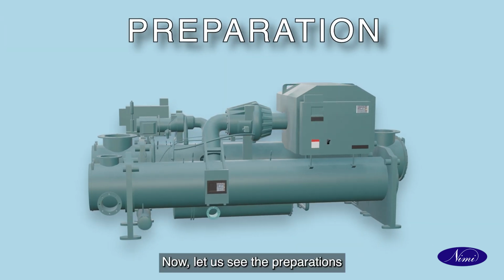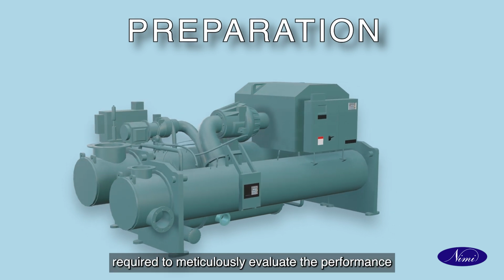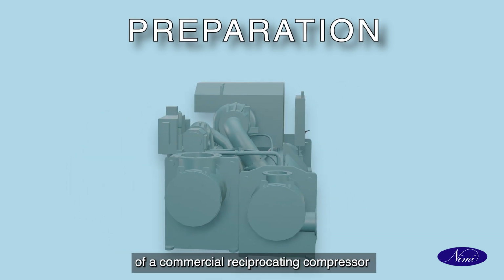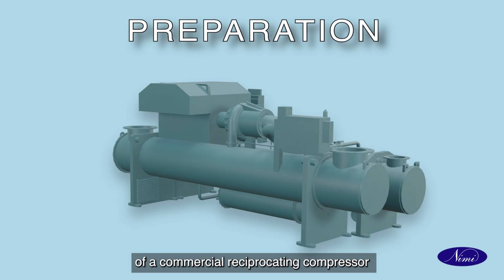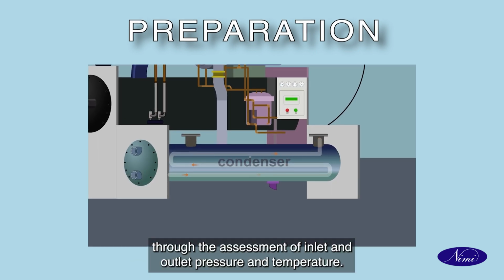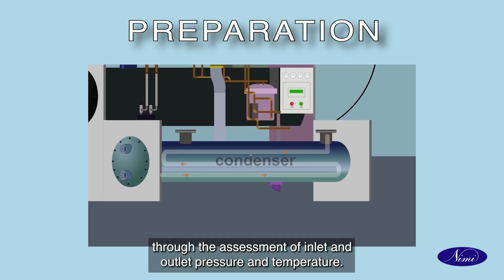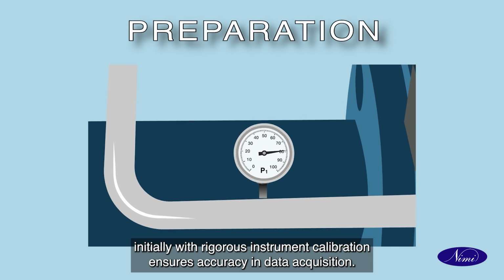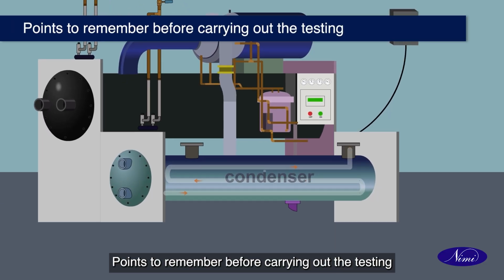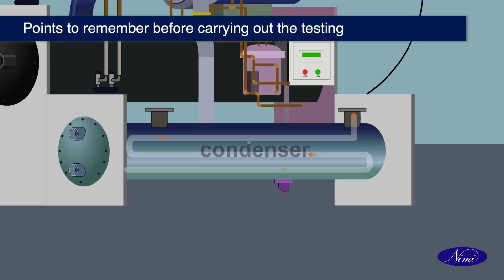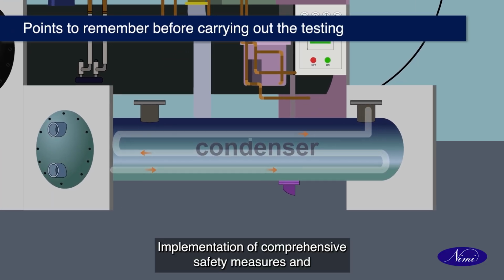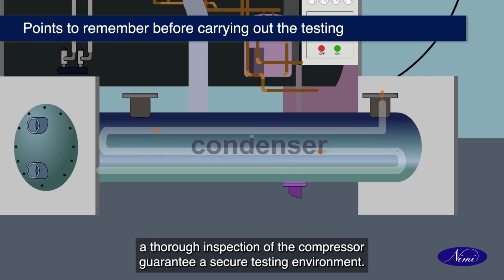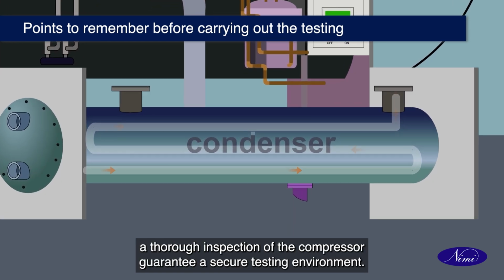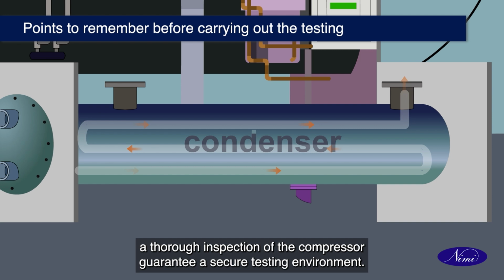Now, let us see the preparations required to meticulously evaluate the performance of a commercial reciprocating compressor through the assessment of inlet and outlet pressure and temperature. Initially, rigorous instrument calibration ensures accuracy in data acquisition. Points to remember before carrying out testing. Implementation of comprehensive safety measures and a thorough inspection of the compressor guarantee a secure testing environment.